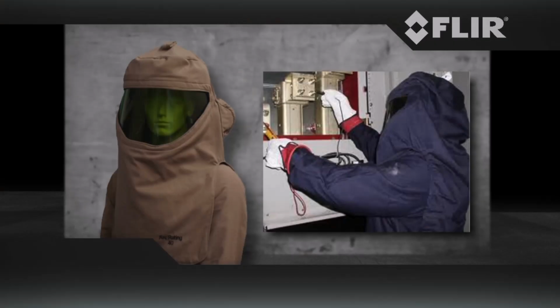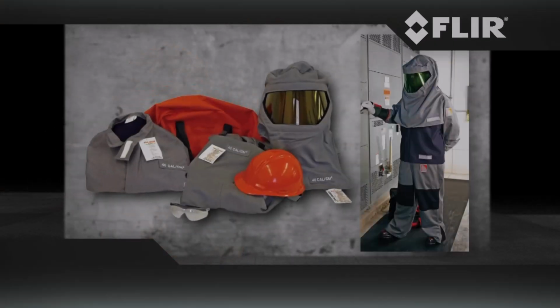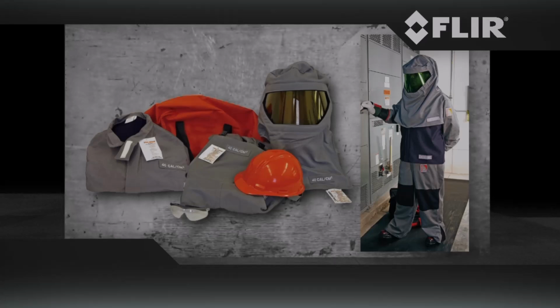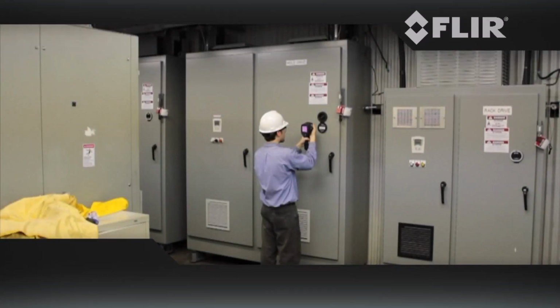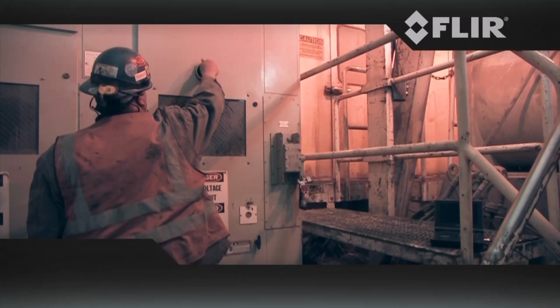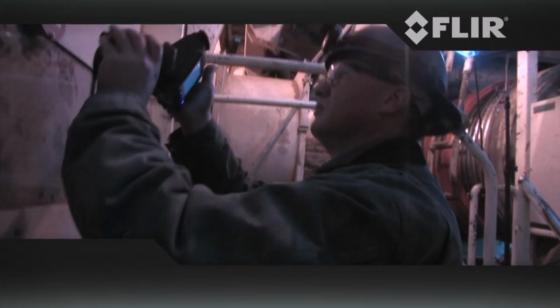Infrared windows are a common way to enable inspection of low, medium, and high voltage electrical cabinets without needing to remove the panel. If we avoid opening the panel, we also avoid the need to suit up in cumbersome arc flash gear. Periodic inspections of critical electrical infrastructure is a key part of keeping your facility safe and productive.